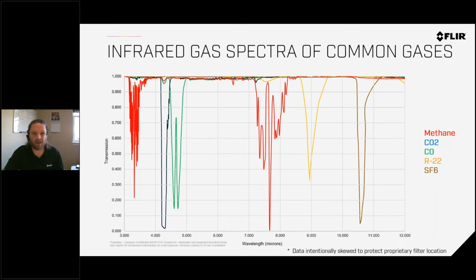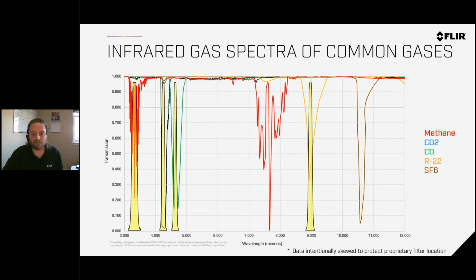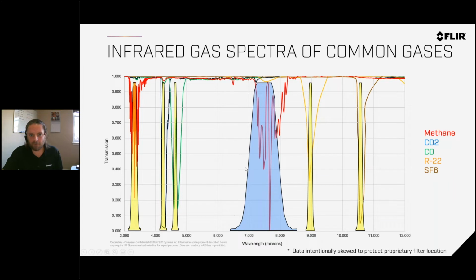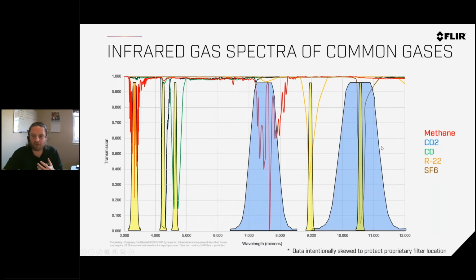Here's another look at a couple of different gases. Again, we have OGI cameras for very specific gases. This GF77 really takes into account a couple of the main gases that you'll find in power generation and manufacturing. In the spectrum of about 7 to 8.5, and then from about 9.5 to 12, that's where we're going to see most of our methane and our SF6, which are the primary gases that this camera can find.